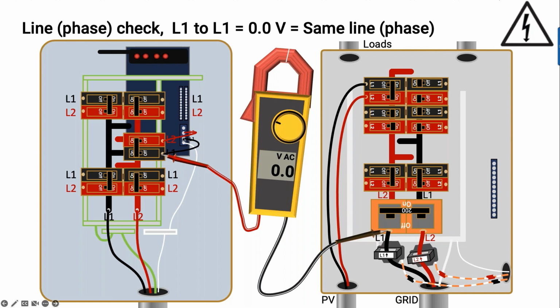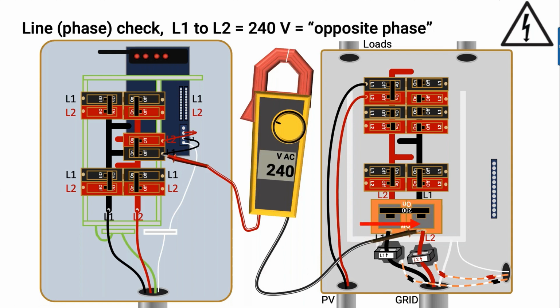You see this is line 1, and these should be the same phase, right? If this is line 1, this should be line 1. If you put this to volts AC and these are the same phase, then it's going to read 0 volts, because essentially it's the same wire all the way through. Now, if something has been reversed, if wires are crossed somewhere through the system, then what you're going to read is 240 volts, because you're measuring across phases as opposed to the same phase.